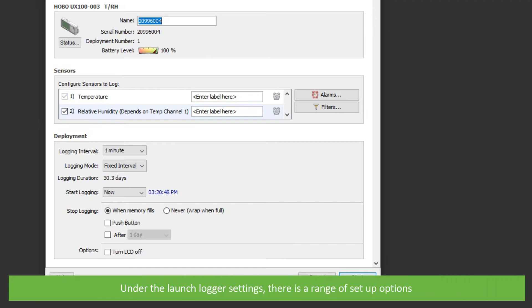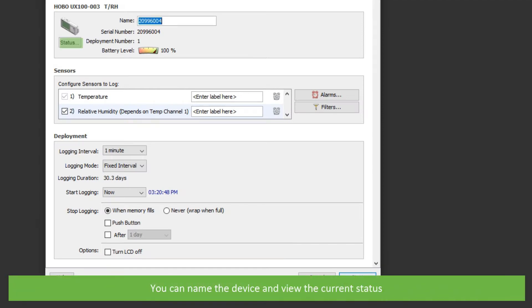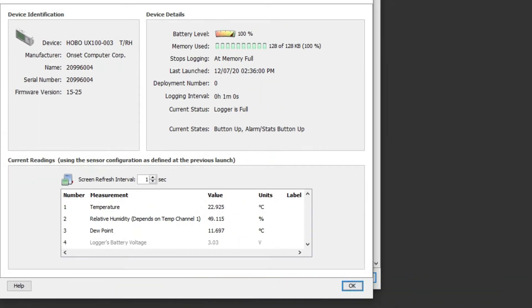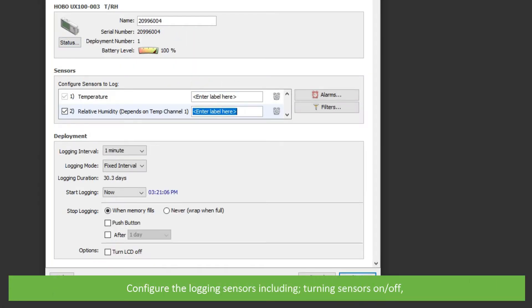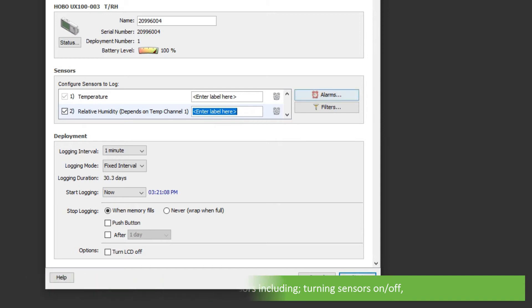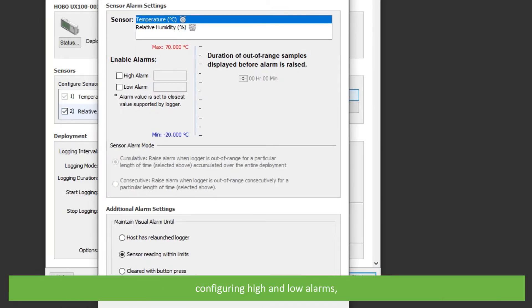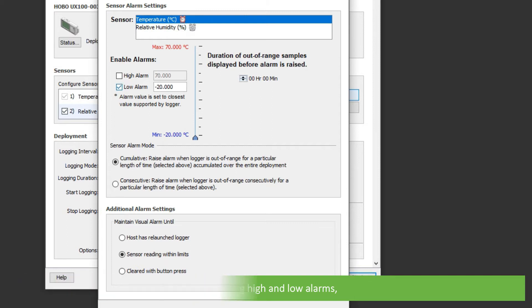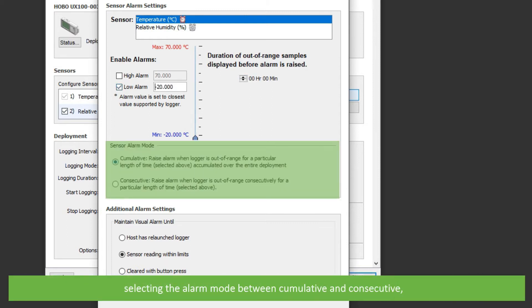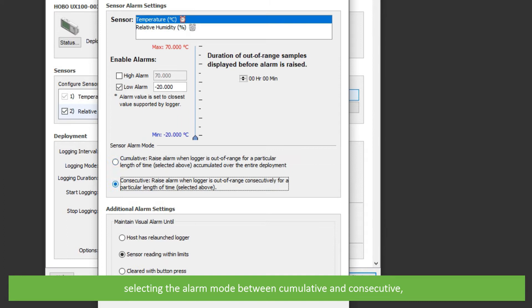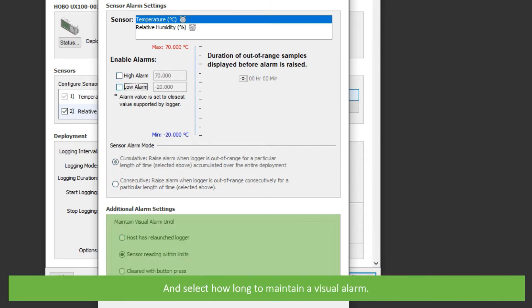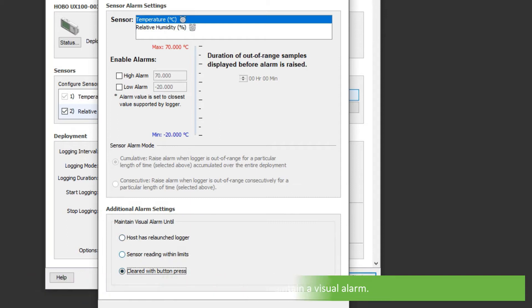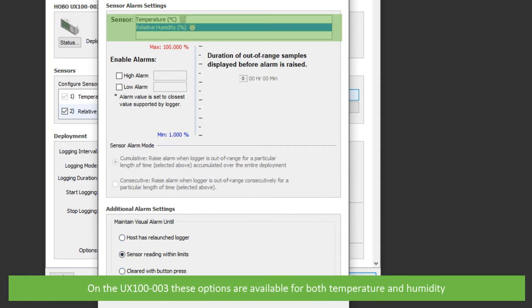Under the launch logger settings there is a range of setup options. You can name the device and view the current status. Configure the logging sensors. This includes turning sensors on or off, configuring high or low alarms, selecting alarm mode between cumulative or consecutive, and select how long to maintain the visual alarm. On the UX100-003, these options are available for both temperature and humidity.